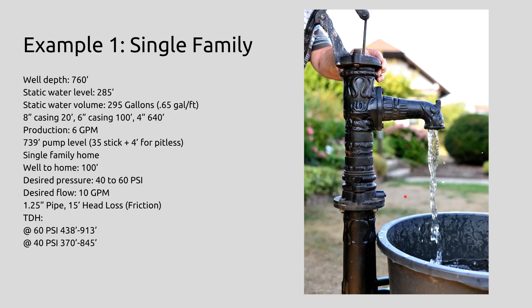So example one, we've got a single family with a well that is 760 feet deep, static water level 285 feet. Our total volume in the well, we've got 295 gallons of pumpable water basically at any given time when the well is full. We've got eight inch casing for the first 20 feet and a six inch casing for the next 100 feet, and then it goes down to a four inch casing for the remainder of the depth. This is a pretty deep well, and it's pretty common to transition to a cheaper PVC type four inch casing. This well is pretty low producing at six gallons per minute, and that kind of shows in the depth — generally, if you get good water, you don't go deeper.